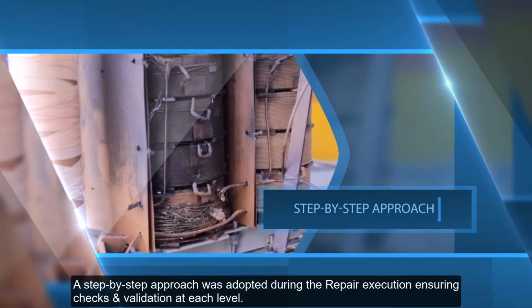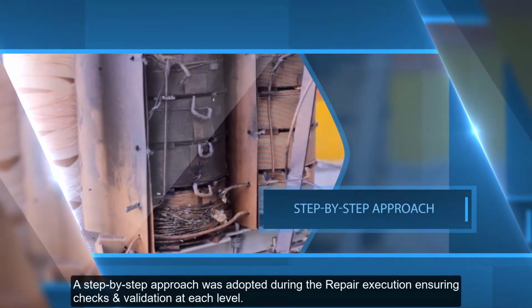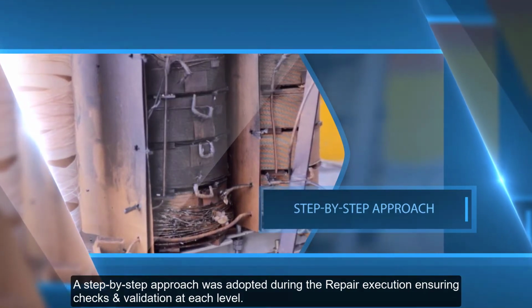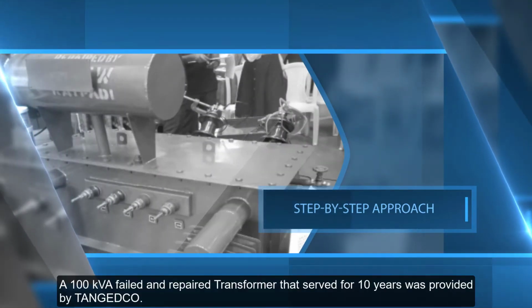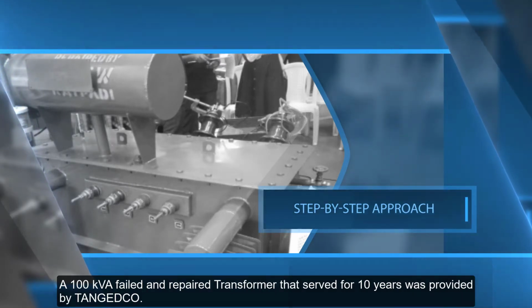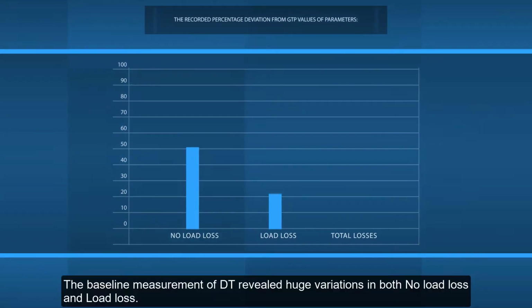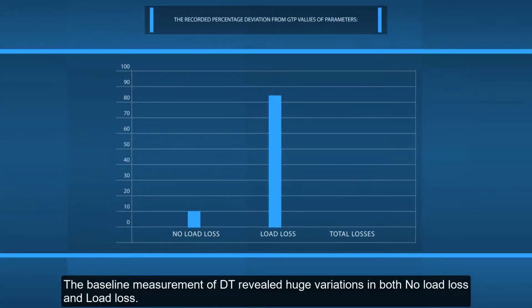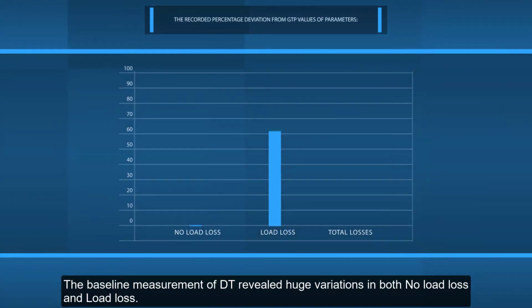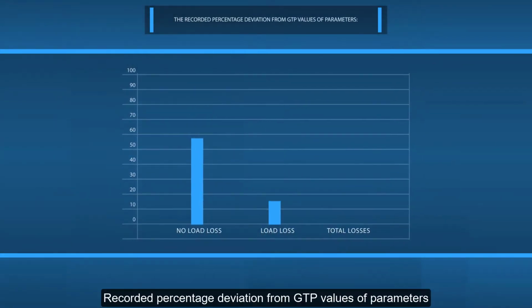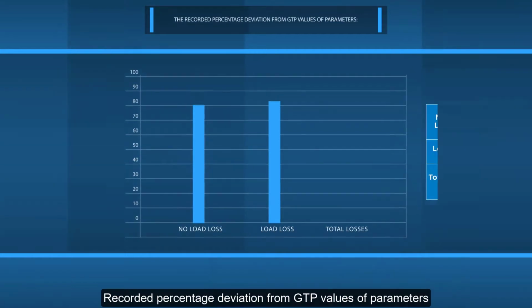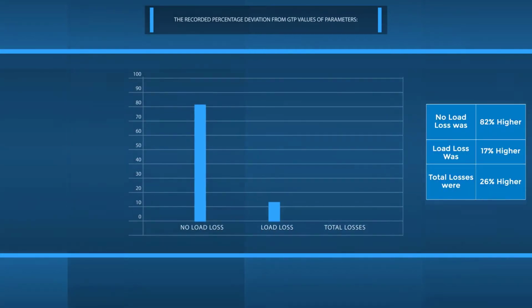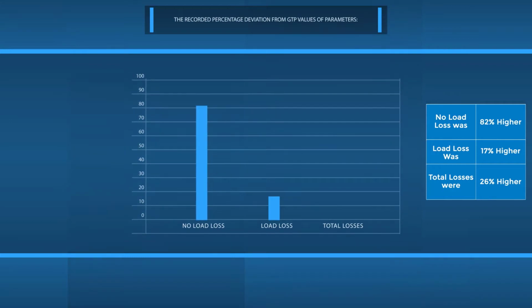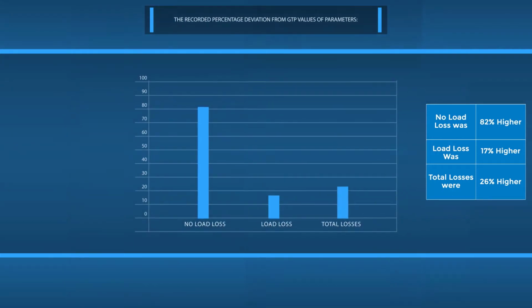A step-by-step approach was adopted during the repair execution, which ensured checks and validation at each level. A 100 kVA failed and repaired transformer that served for 10 years was provided by TANGEDCO. The baseline measurement of the DT showed huge variations in both no-load loss and load loss. The recorded percentage deviations from GTP values of parameters were: no-load loss was 82% higher, load loss was 17% higher, and total losses were 26% higher.